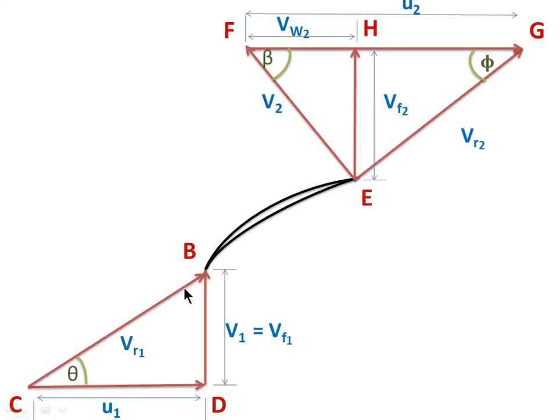We can now draw the inlet and outlet velocity triangles for the centrifugal pump. These are backward curved vanes. At the inlet velocity triangle, angle alpha is 90 degree because in a centrifugal pump water enters radially at inlet — the absolute velocity V1 makes an angle of 90 degree with the direction of motion of the impeller U1. This means Vw1 equals 0, so V1 equals Vf1.